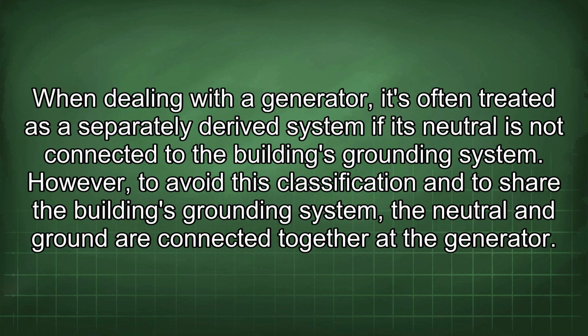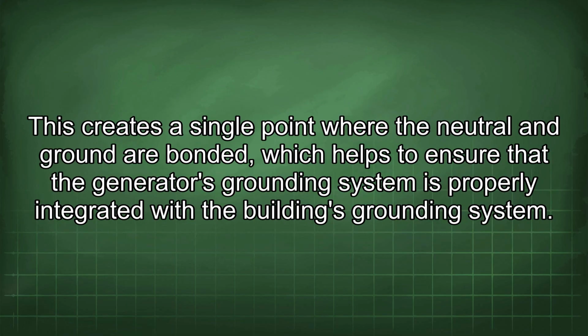When dealing with a generator, it's often treated as a separately derived system if its neutral is not connected to the building's grounding system. However, to avoid this classification and to share the building's grounding system, the neutral and ground are connected together at the generator. This creates a single point where the neutral and ground are bonded, which helps to ensure that the generator's grounding system is properly integrated with the building's grounding system.